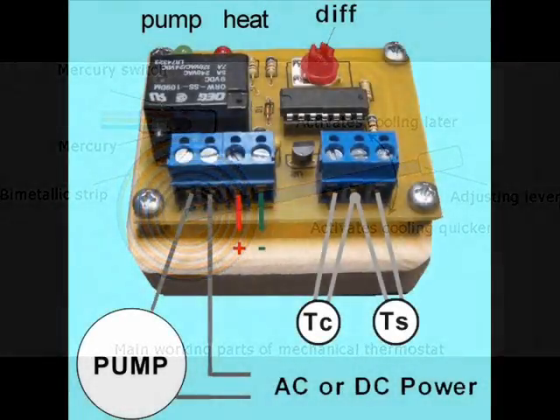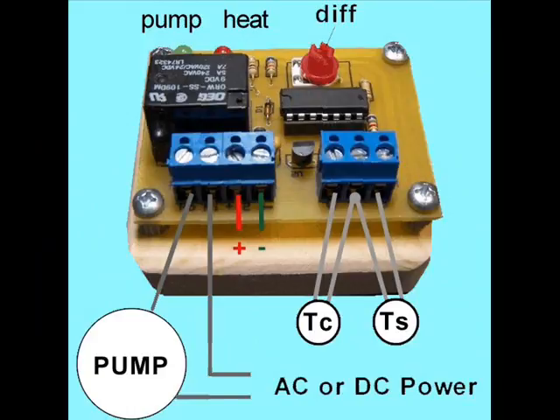Differential controllers are different than adjustable controllers. They use two temperature sensors rather than one. The difference in temperature between the probes is used to control the relay. The relay in turn activates a pump or other devices. This is how active heat gain from sunlight is accomplished.